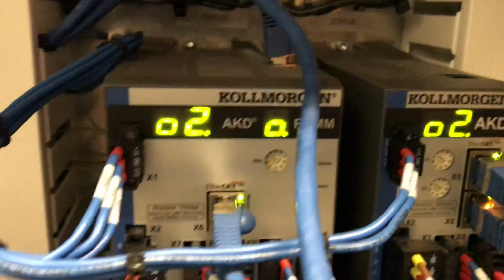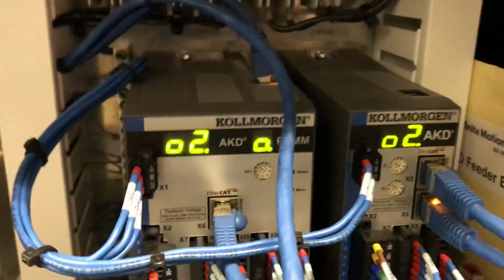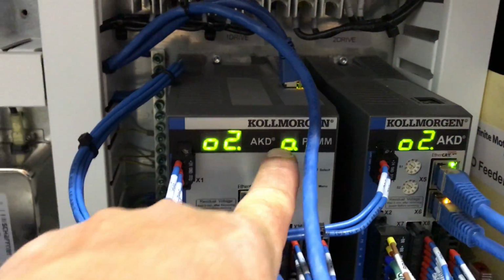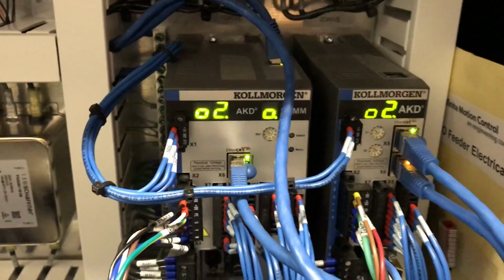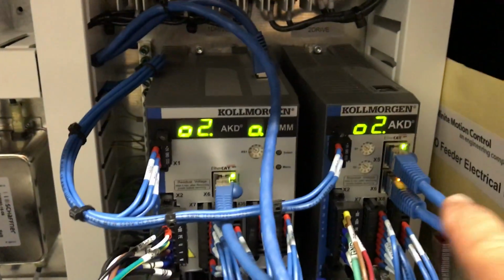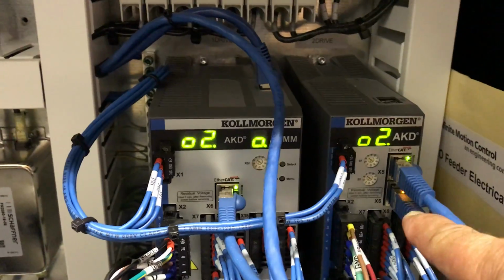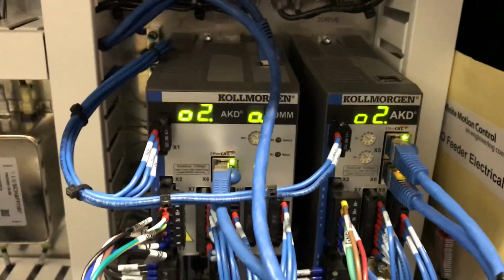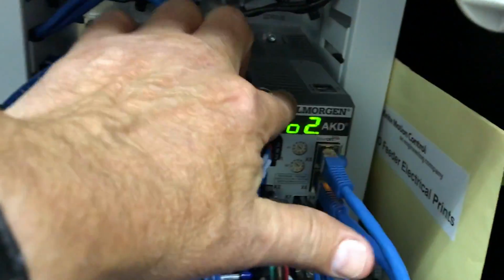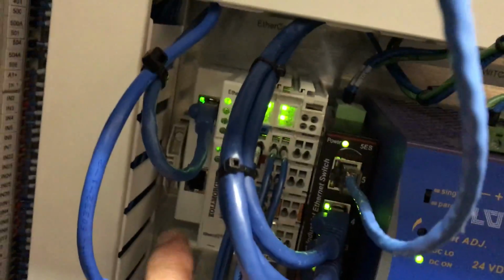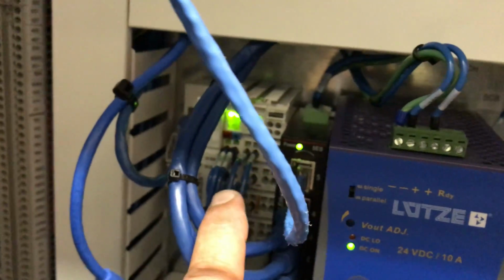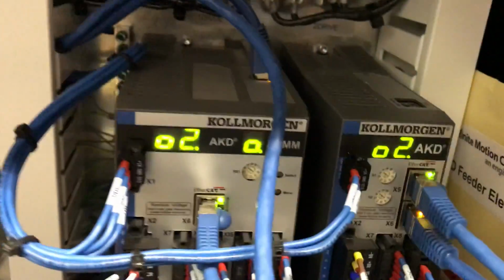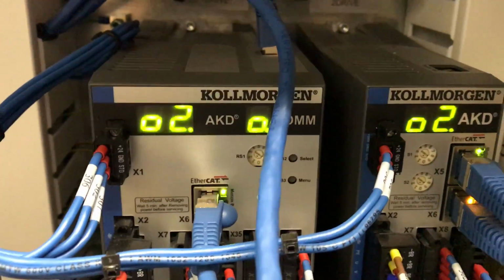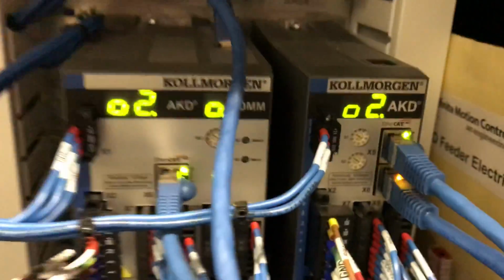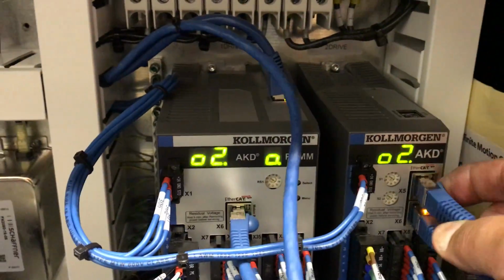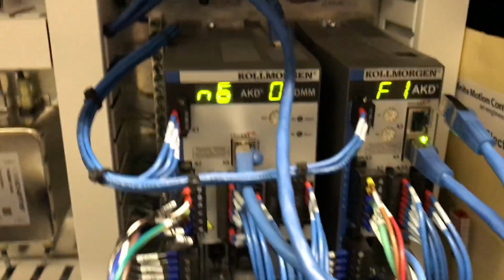Now there are other faults, there are error codes. These are more serious. Error codes will be shown right here. For instance, I'll create one. This is the EtherCAT. This is the communications that runs the drives. In this system we have the PDMM, we have a slave drive, and then over here we also have remote I/O. That's a remote I/O block. So the system always wants to see a proper configuration consisting of all these devices. So right now I'm just going to unplug one of them, and as you can see, it all stops.